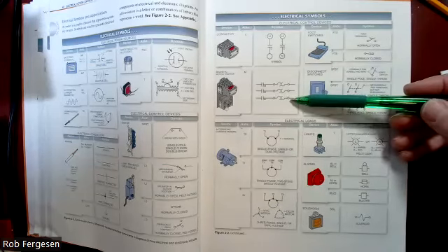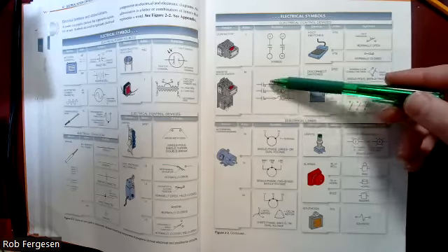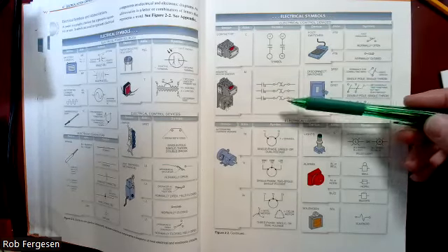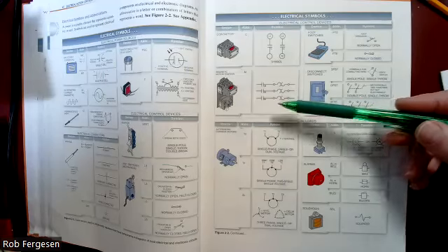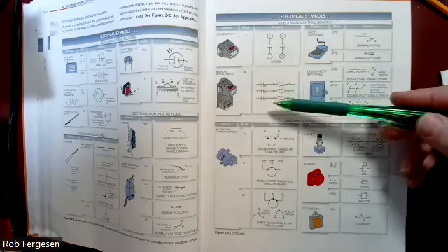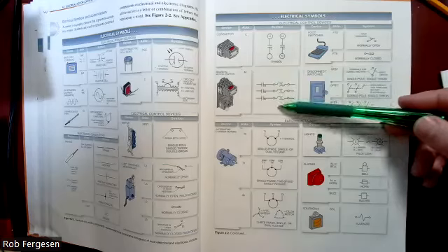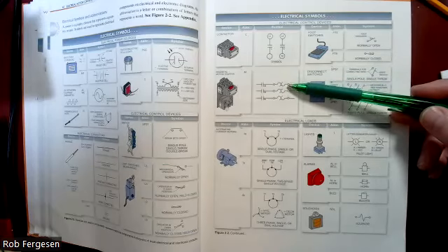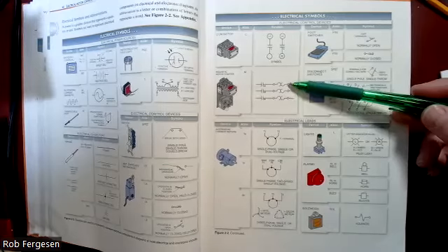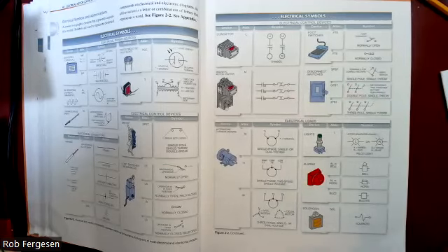A motor starter is the same as a contactor. This is showing 3 different wires because the motor starter they're showing is for a 3-phase motor, so it needs 3 different wires. It's showing you the contacts, and it's showing you the overload connections. These little question marks upside down and backwards against each other are called overloads. It's very important to know what that symbol is. That means when you have too much current flowing through that wire, they will pop open and disconnect it. You basically disconnect that wire in that circuit.